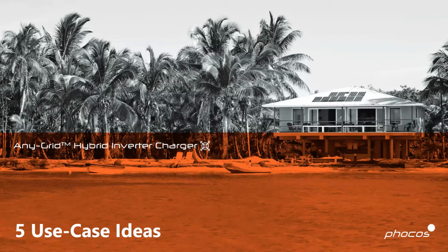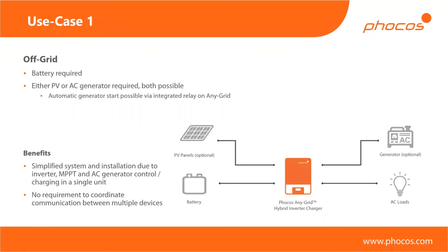Another question, I think it's easiest if I just answer the question as I go along, is whether anti-islanding protection is available. It cannot, because it wouldn't make any sense. The whole point of this device is to be able to work off-grid, which by definition is an island. So when it disconnects from the grid, it's galvanically isolated from the grid. There's no connection between neutral or line and the grid, and that by definition is an island.